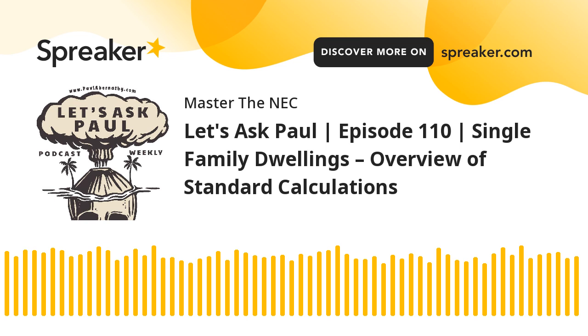Now, the small appliance branch circuits are going to be something that's covered in 210.11C1. That's going to tell you that you have to have at least 2 small appliance branch circuits. They have to serve the countertop, and it's also going to cover the receptacles that are in the kitchen, in a pantry, in a dining room. Now, I can always have more than 2, but I got to have at least 2.